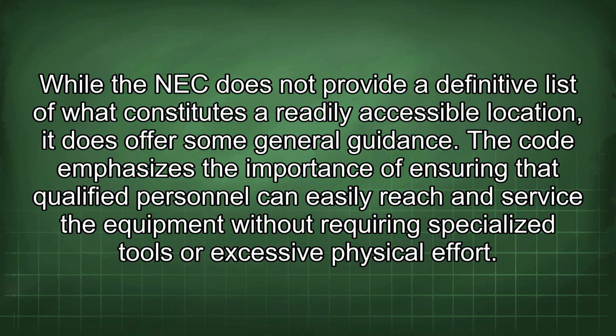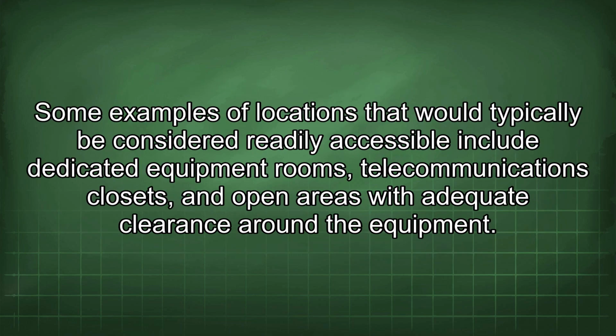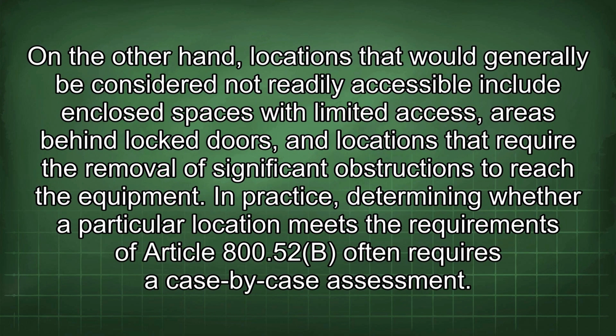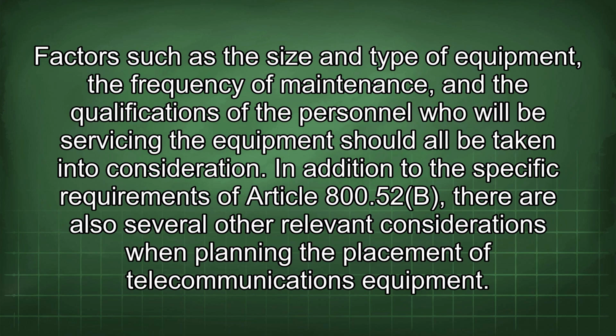While the NEC does not provide a definitive list of what constitutes a readily accessible location, it does offer some general guidance. The Code emphasizes the importance of ensuring that qualified personnel can easily reach and service the equipment without requiring specialized tools or excessive physical effort. Some examples of locations that would typically be considered readily accessible include dedicated equipment rooms, telecommunications closets, and open areas with adequate clearance around the equipment. On the other hand, locations that would generally be considered not readily accessible include enclosed spaces with limited access, areas behind locked doors, and locations that require the removal of significant obstructions to reach the equipment. In practice, determining whether a particular location meets the requirements of Article 800.52b often requires a case-by-case assessment. Factors such as the size and type of equipment, the frequency of maintenance, and the qualifications of the personnel who will be servicing the equipment should all be taken into consideration.